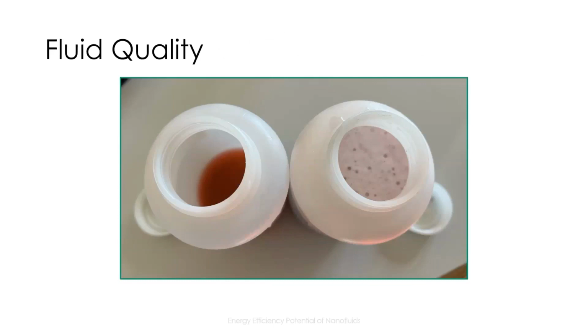A note on the fluid quality: this photo highlights a foaming issue that we found on site. On the left-hand side is an optimal fluid condition that was taken from our air-cooled chiller site, and the right-hand sample shows foaming where air wasn't able to be properly purged from the system. And this foaming, as confirmed by the manufacturer, really inhibits heat transfer, and some steps were made to mitigate this. However, the issue hasn't been completely resolved even to this late date. Therefore, due to both the loading and this foaming issue, we're not sure whether we can really trust the data that came out of this site.